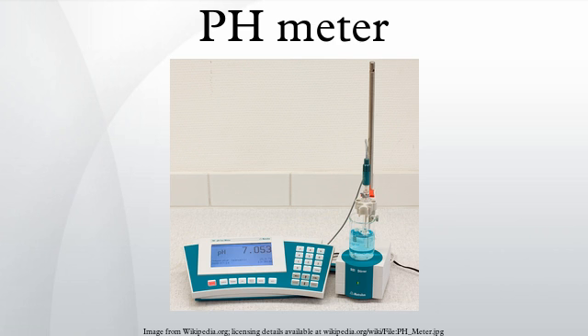After each single measurement, the probe is rinsed with distilled water or deionized water to remove any traces of the solution being measured, blotted with a scientific wipe to absorb any remaining water which could dilute the sample and thus alter the reading, and then quickly immersed in another solution.